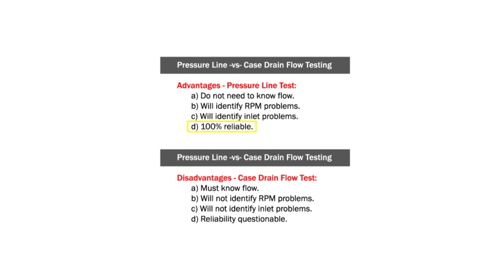A pressure line test is 100% reliable. As you have just witnessed, a case flow test's reliability is questionable. If you do a case flow test, did you actually see the true condition of the pump — or was the oil you were looking for going back to the intake of the pump, giving you a false positive on the condition of your pump?